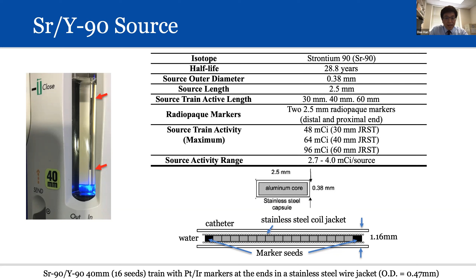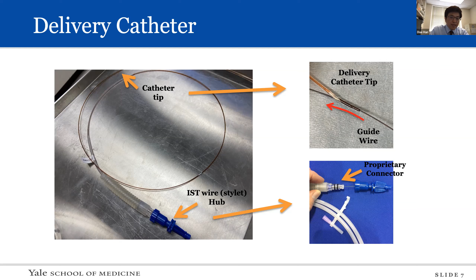This shows the delivery catheter, and the delivery catheter tip has a hole for the guide wire to pass through, and the delivery catheter follows the guide wire to the treatment lesion as a monorail. The IST wire, which is the indicator of source train wire, is already inserted in the delivery catheter when it comes out from the sterile package. So the IST wire provides 3 different functions. The first one is indicating expected source positions under fluoroscopy. Number 2 is providing delivery catheter rigidness. And number 3, delivery catheter damage check. I will explain in later slides.